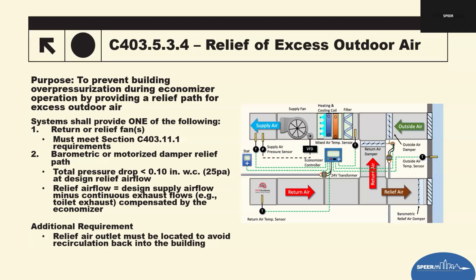So option 1, return or relief fan. So the first compliance path is using either one of those, a return fan or dedicated relief fans. These fans remove excess air and maintain proper building pressure. To comply, they must meet the requirements found in Section 403.11.1, which covers fan efficiency and control requirements.